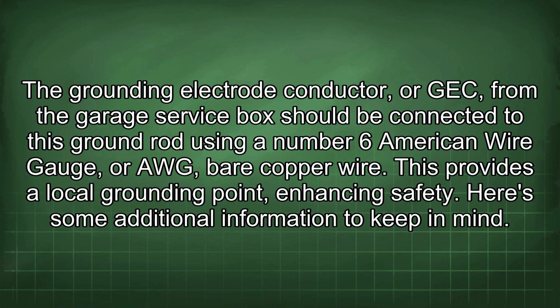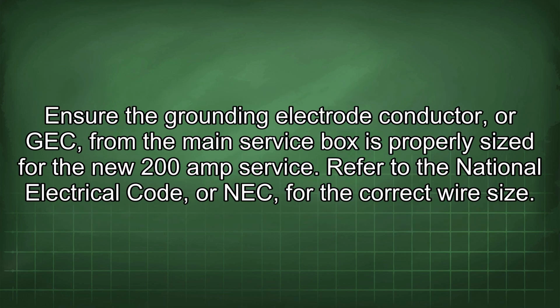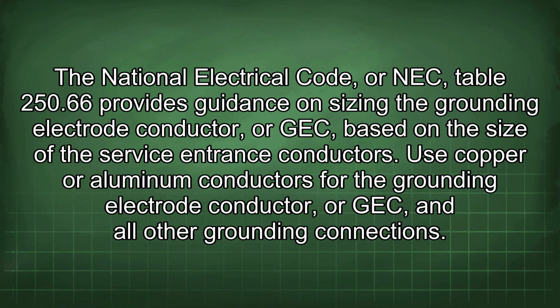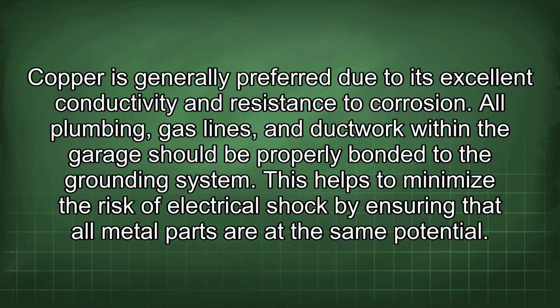Here's some additional information to keep in mind. Ensure the grounding electrode conductor, or GEC, from the main service box is properly sized for the new 200 amp service. Refer to the National Electrical Code, or NEC, for the correct wire size. NEC Table 250.66 provides guidance on sizing the GEC based on the size of the service entrance conductors. Use copper or aluminum conductors for the GEC and all other grounding connections. Copper is generally preferred due to its excellent conductivity and resistance to corrosion.